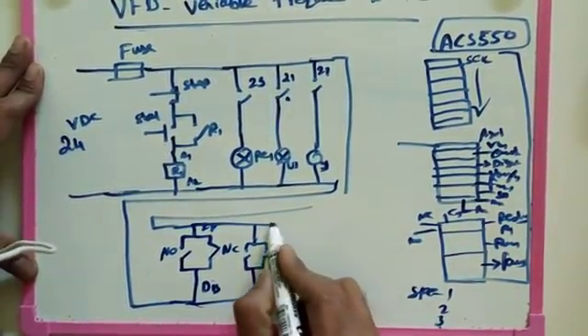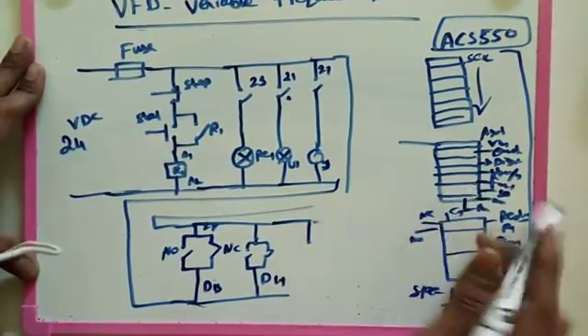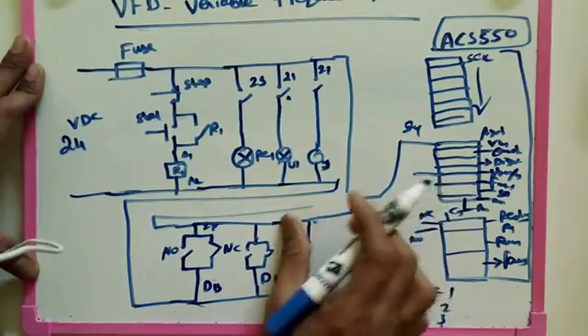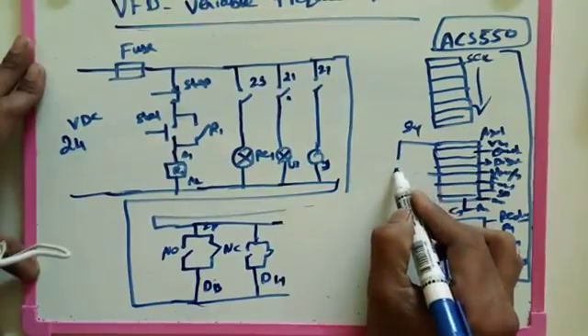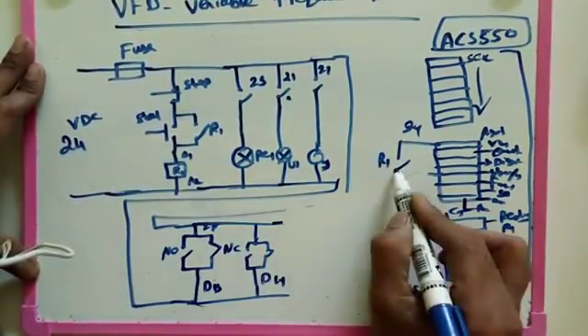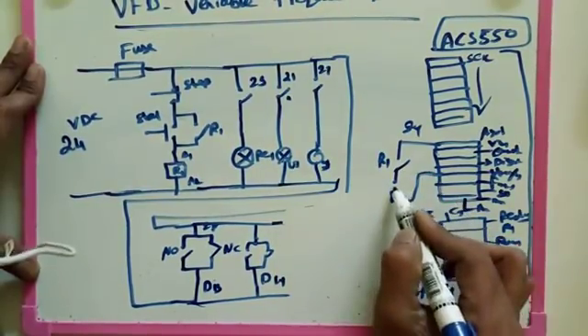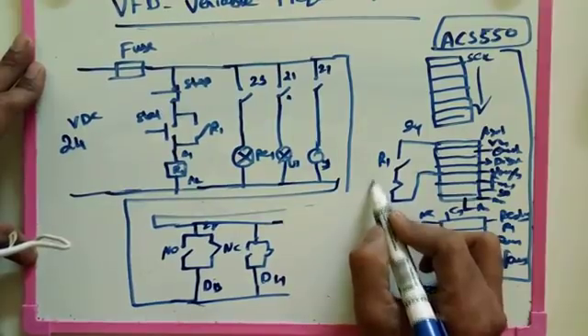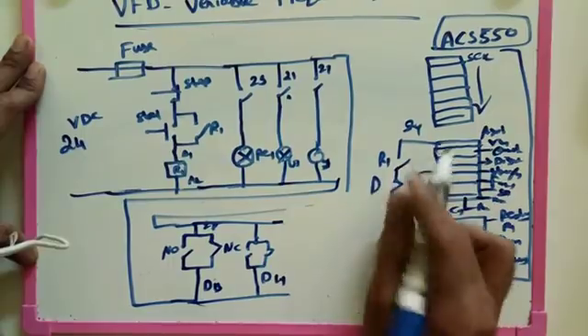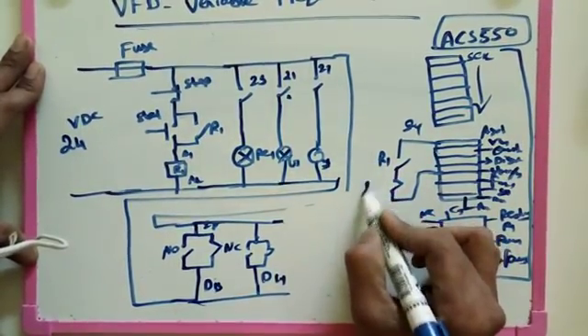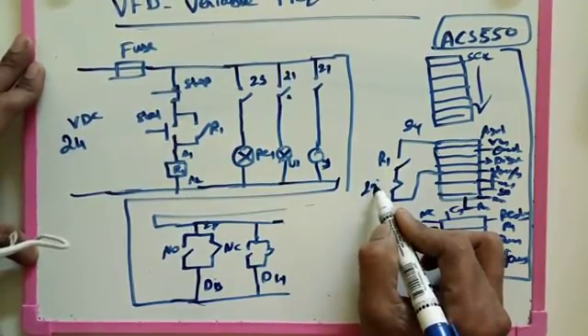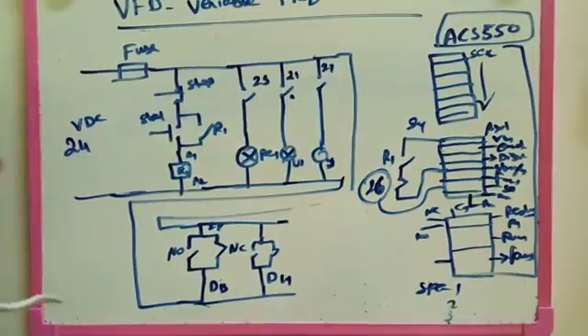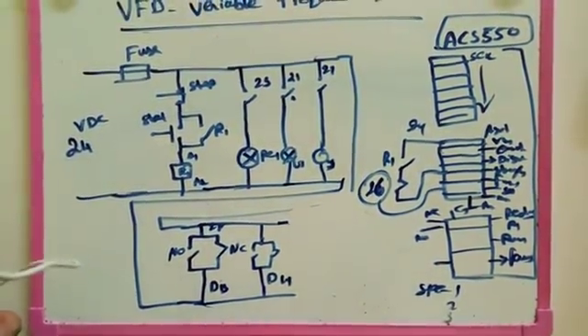We also need to control the on-off system on the VFD. We use relay R1 NO contact and the NC contact of the fault relay, connecting to terminal 26 on the VFD. We had already connected terminal 27 previously. This completes terminal 2 — the start-stop and fault-finding portion of the control diagram. If you have any doubts please comment, I will help you. Thank you for watching.